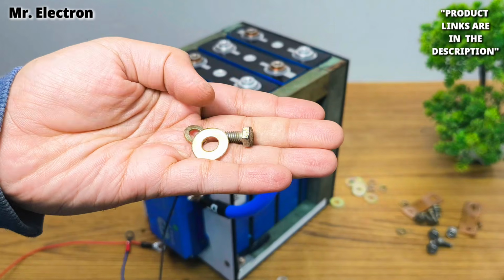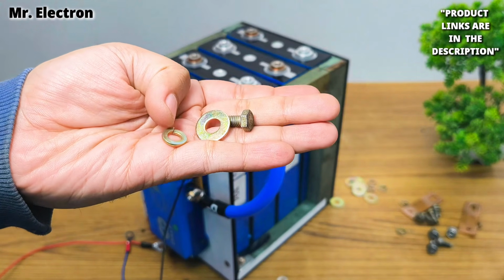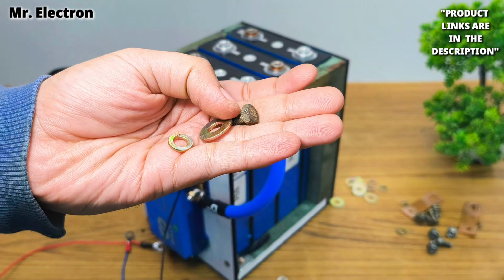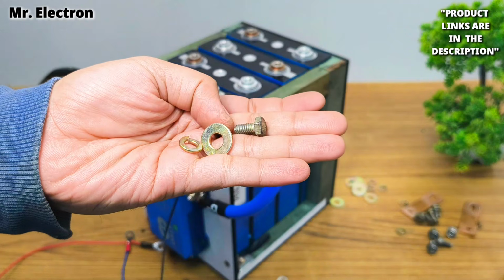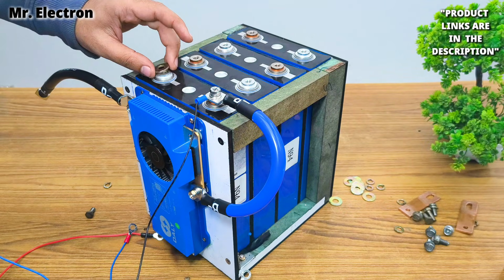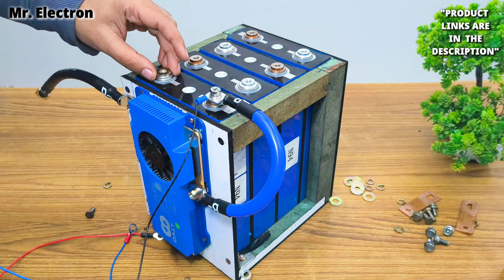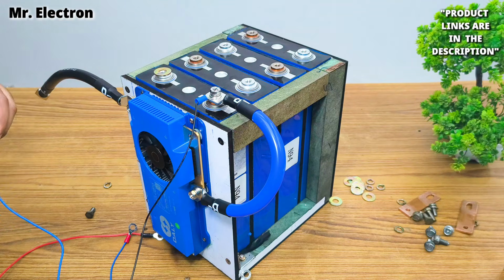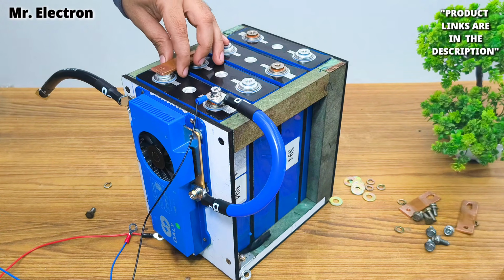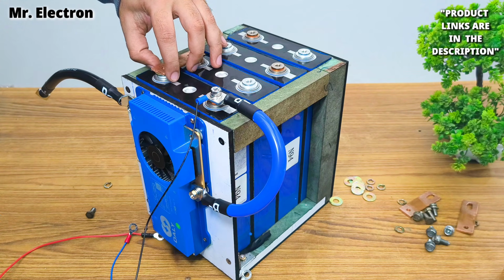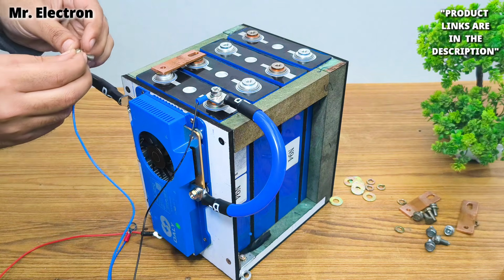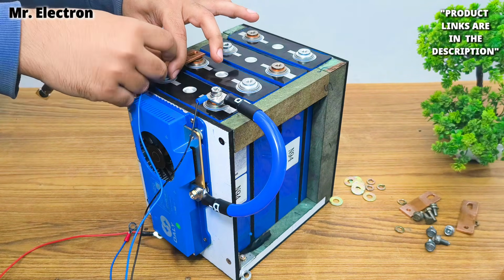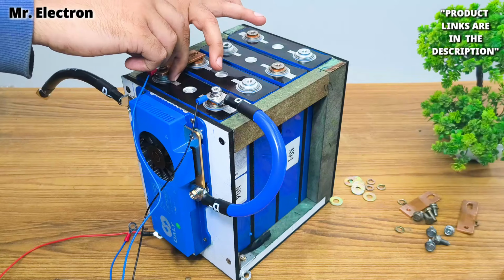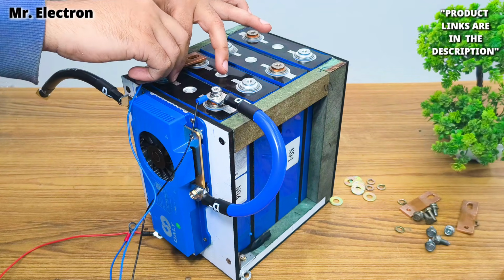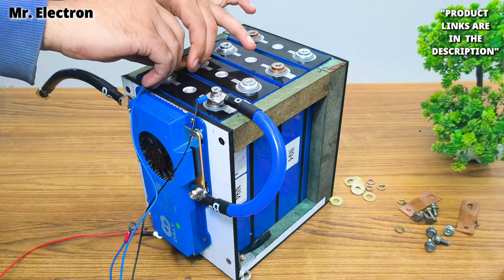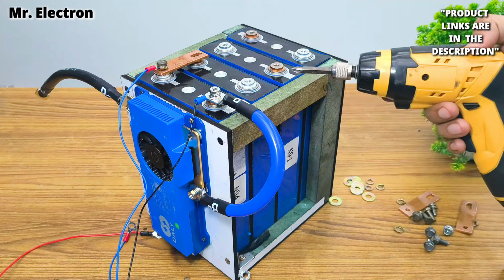I've taken one washer of this cut type, and a bolt. Let's install these. The process: here is the aluminum terminal, placed like this—I've already sanded the terminals, which is a must. After that comes the bus bar, placed like this, then the wire I mentioned, then the cut-type washer, and here it goes. It's loosely connected right now; after that, I'll tighten it with the electric screwdriver.